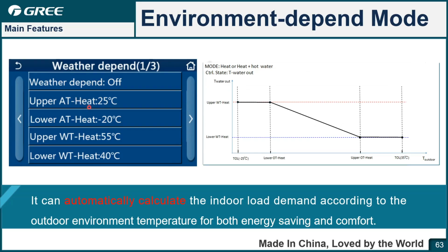So here is the upper limit ambient, lower limit ambient, and this is the upper limit for water temperature, lower limit for water temperature. For example, if the ambient changes in this range, the water temperature will also change along this line. However, if the ambient is lower than this value, such as very cold, in this case the water temperature will be high to satisfy the customer. However, if the ambient is very high, higher than this certain value, then the water temperature will stay at this value, so that the unit can automatically adjust the water temperature according to the ambient temperature change, and the power consumption will be reduced.